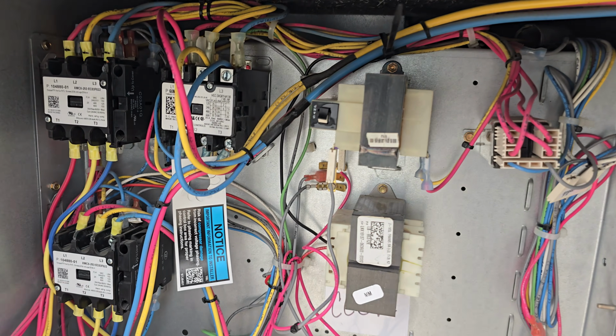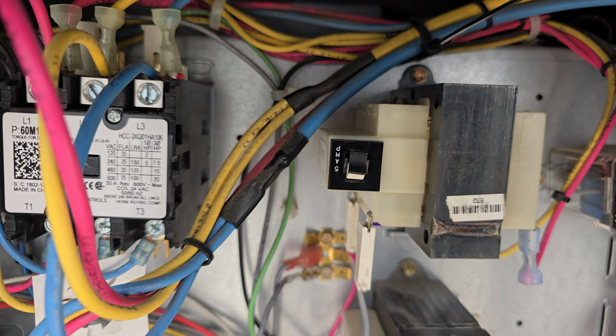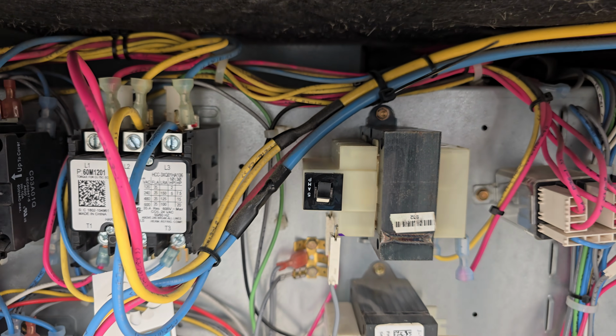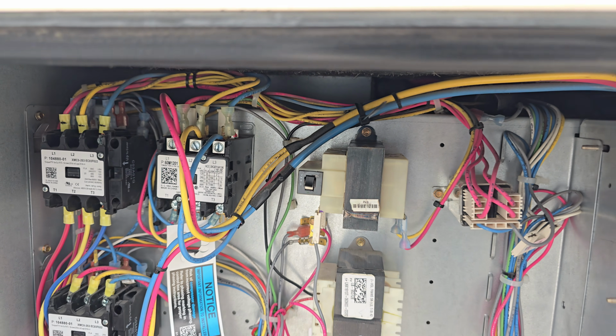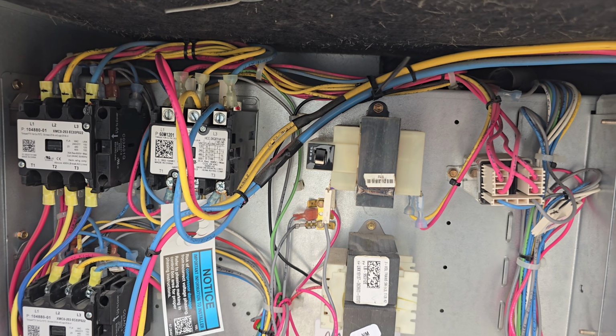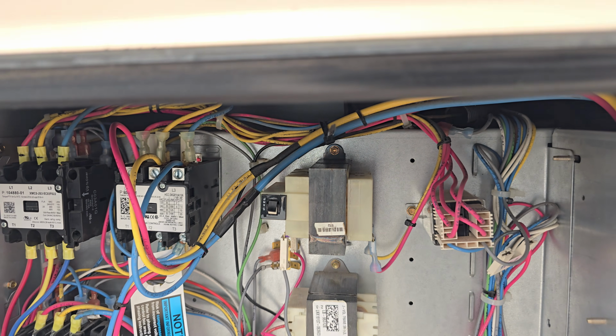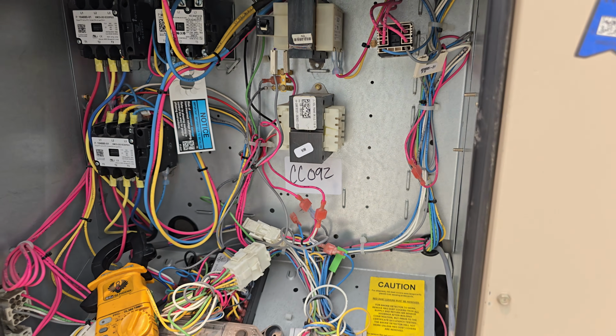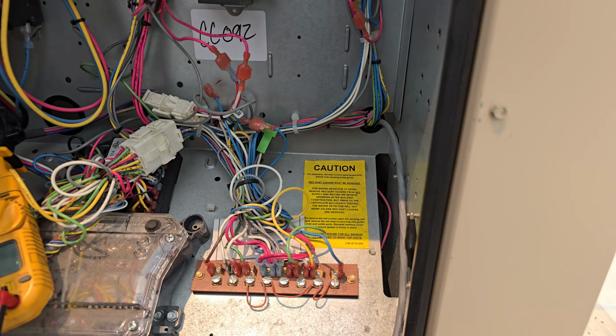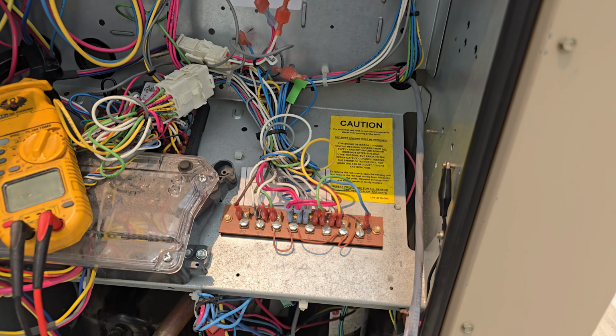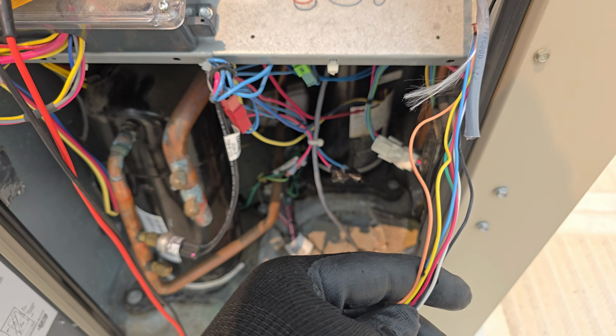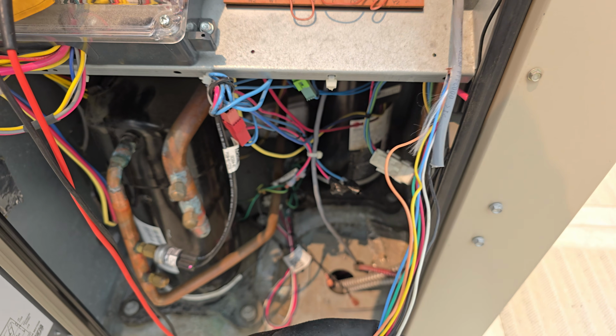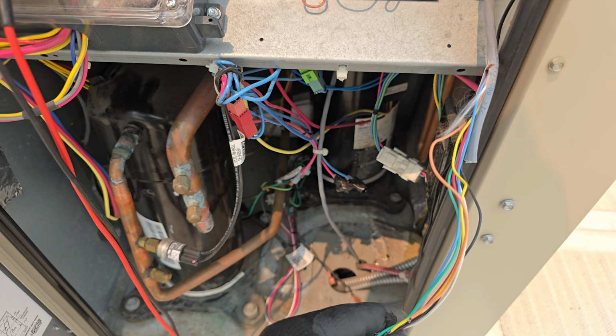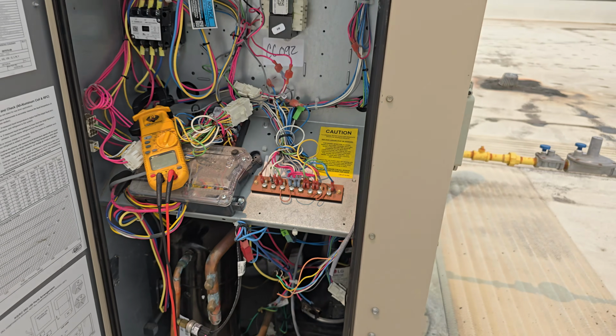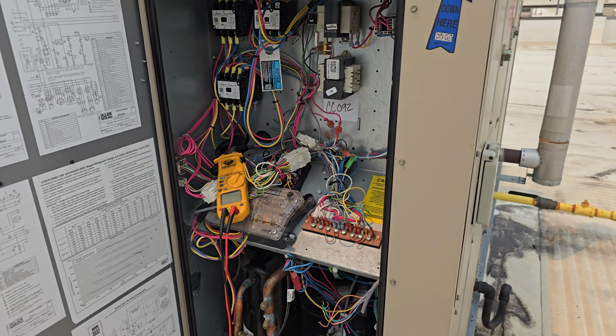Again, before you realize it, my fuse trips off. My fuse at the transformer is tripping off. So it means the problem is not coming from my thermostat wire. So this is solved, eliminated. I'm going to go to the next, and I will keep you posted.